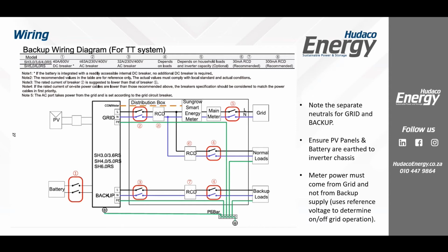Okay, so this is any plugs that are on your backup loads, and this is any plugs that are on your normal loads. Okay, here again, you could split this and you could have another section without your RCD that's feeding lights. Okay, and then here you see they've used 2 breakers here. You don't have to use 2 breakers. You could generally use 1 if this is then going into another board. Then you would have another breaker in the other board.